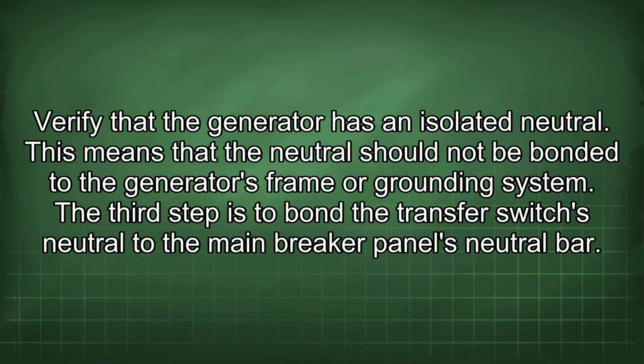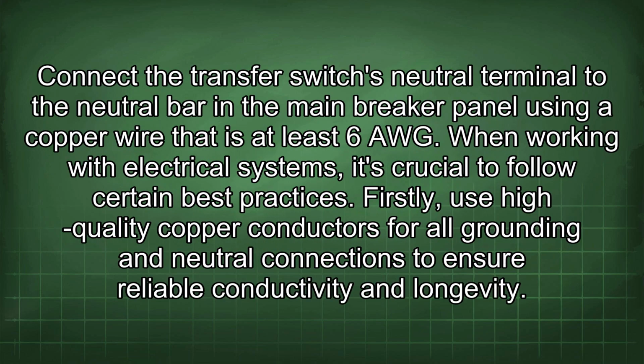Verify that the generator has an isolated neutral. This means that the neutral should not be bonded to the generator's frame or grounding system. The third step is to bond the transfer switch's neutral to the main breaker panel's neutral bar. Connect the transfer switch's neutral terminal to the neutral bar in the main breaker panel using a copper wire that is at least 6 AWG.